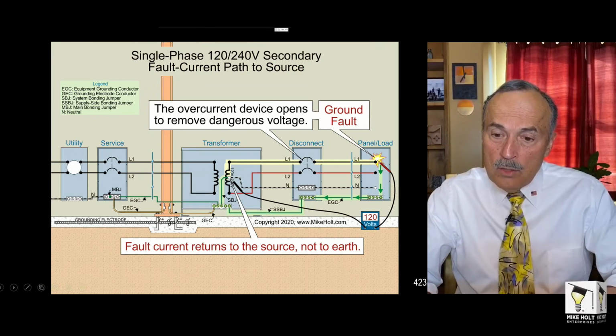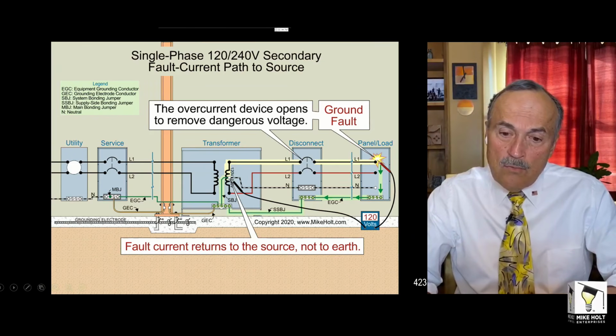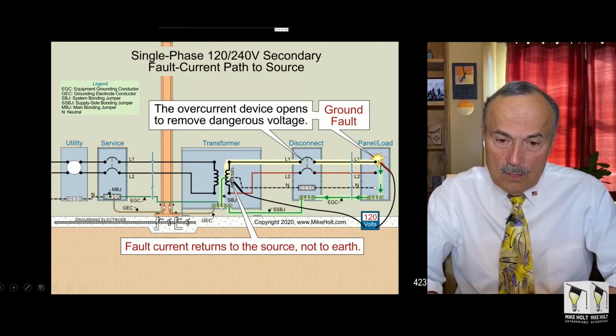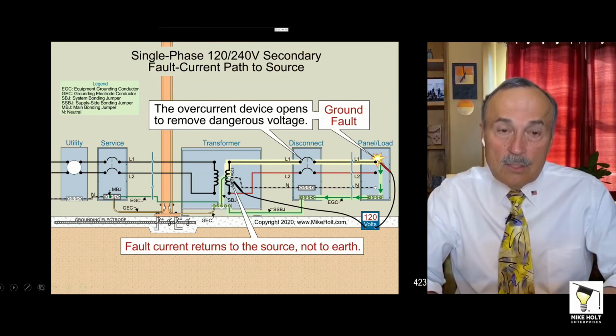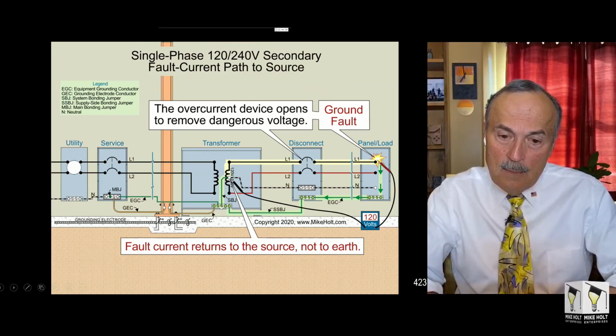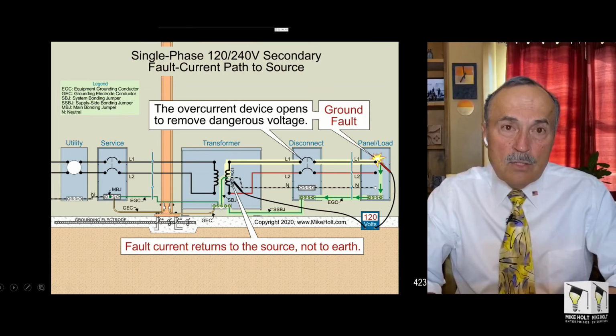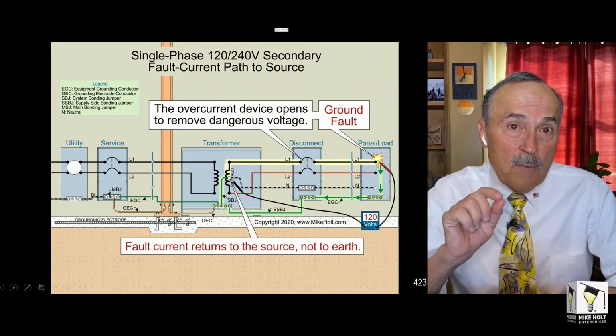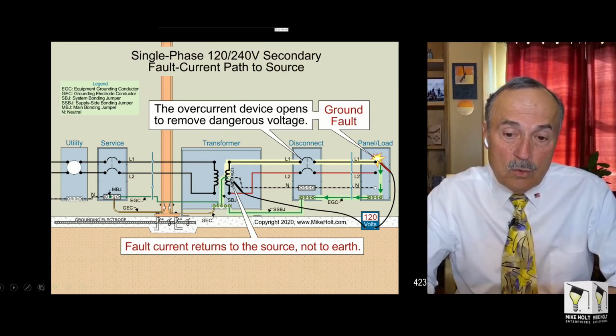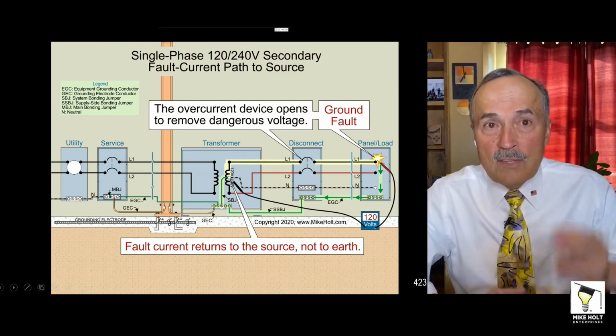Current goes to the enclosure, goes to the equipment grounding conductor. From the equipment grounding conductor, because it's on the supply side of this secondary disconnect, that's a supply side bonding jumper. And then the supply side bonding jumper, and then we have the system bonding jumper. And then, of course, the whole thing is going to be grounded. So now we're grounding the secondary. We're providing a system bonding jumper to provide the effective ground fault current path for that fault current to get back to the source.